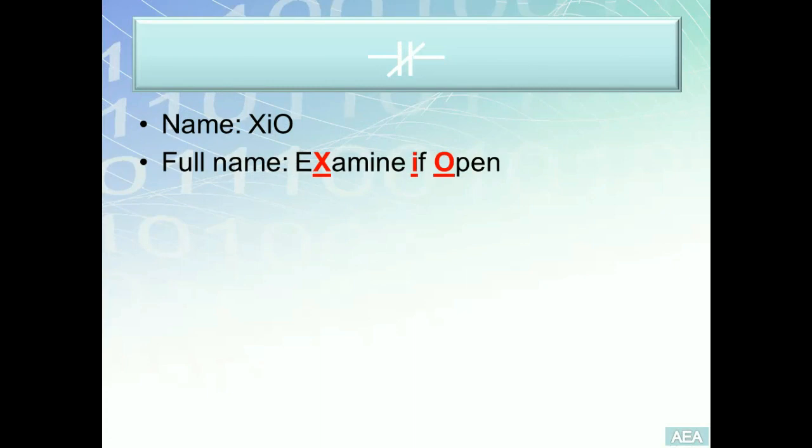The full name is examine if open. From the previous video tutorial we know that an open state input is going to be read in the PLC memory as logic zero, so all this instruction is doing is examining a memory location looking for a zero.